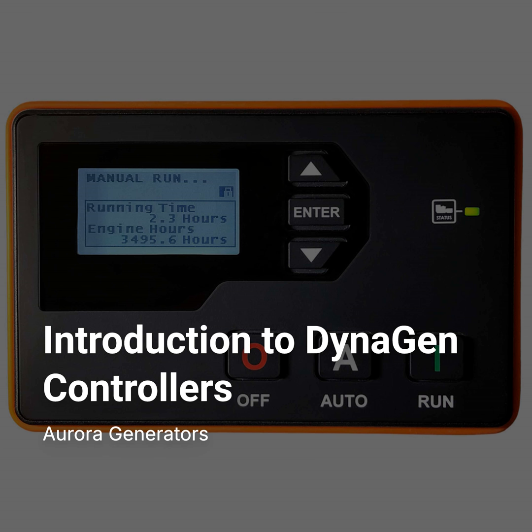For modern electronic engines, speed control can often be done right through J1939 CAN bus. The controller just tells the engine's ECM what speed to run at. Digital commands. Yep, some controllers even let you adjust speed manually from the front panel using the up-down buttons, or maybe via dedicated switched outputs wired to the ECM. Lots of flexibility there. And I saw a specific mention of auto-starting on floats.